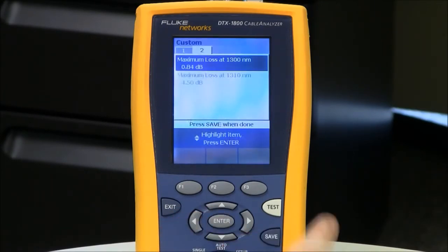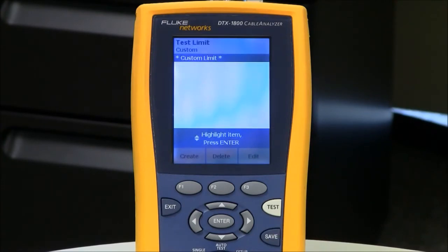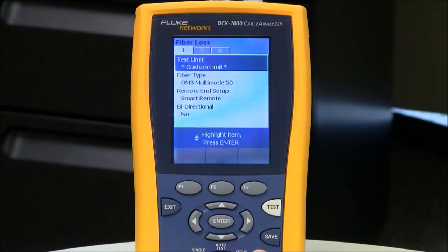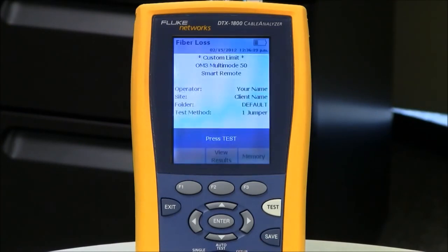Save. Now I hit Save to store it. There is my custom test limit. Hit Enter to select it. Rotate the dial to auto-test. And that is how you create a custom fixed loss limit.